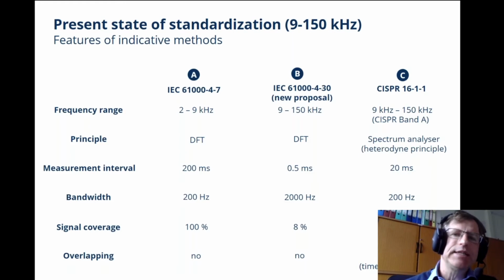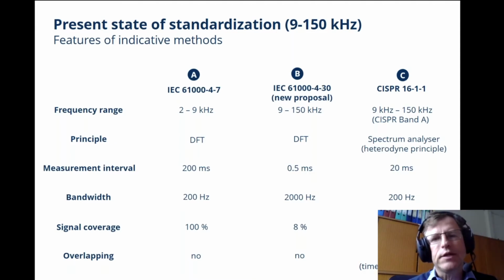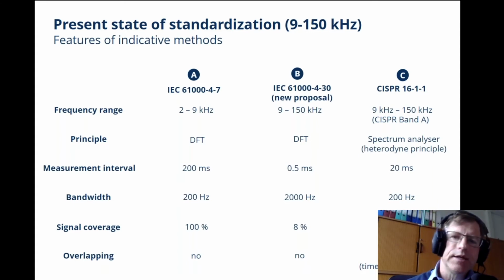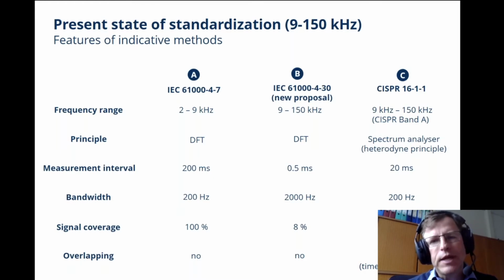The last one is the CISPR 16 method, established for lab measurements. We're strictly talking about CISPR band A, 9 to 150 kilohertz, where originally a spectrum analyzer based on the heterodyne principle is defined, but it can also be done by digital implementation based on FFT. Here the measurement interval is 20 milliseconds. You also have a bandwidth of 200 hertz, but a signal coverage that, due to very high overlap, is much higher than 100%.